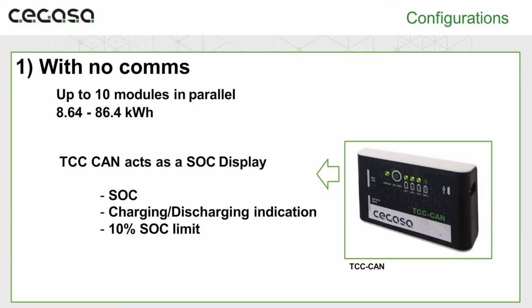In the case of no comms, the TCC-CAN becomes an accessory again. It's not something that you require, but it's advisable to have it, especially when you are setting up, because you can extract information from the batteries. The use is practically the same as the one I explained with the smaller batteries. Most importantly, you get to know the state of charge of the battery at any particular moment, if it's charging or discharging, and all the warnings for the 10% SOC limit. So, it's very similar to the application I explained before.